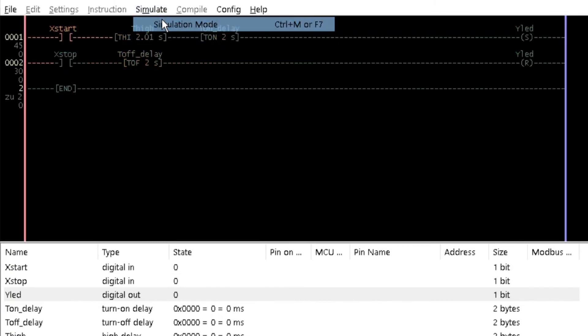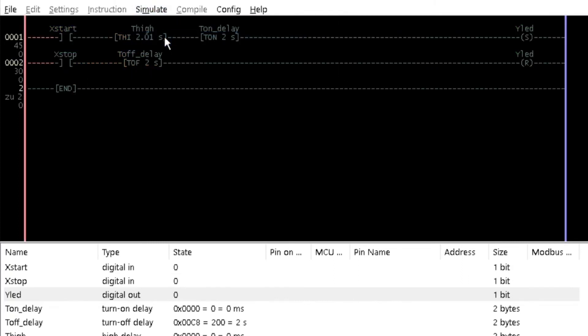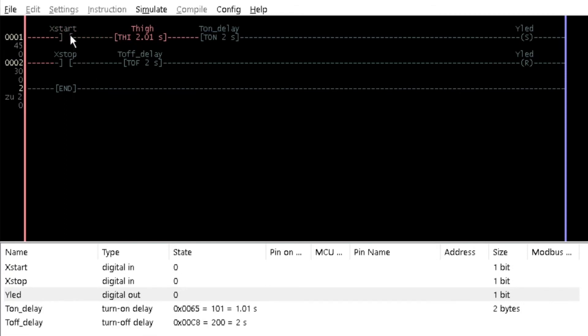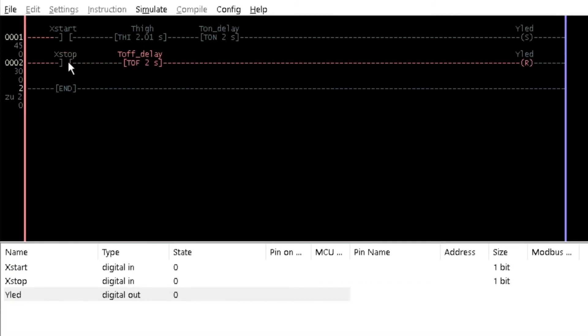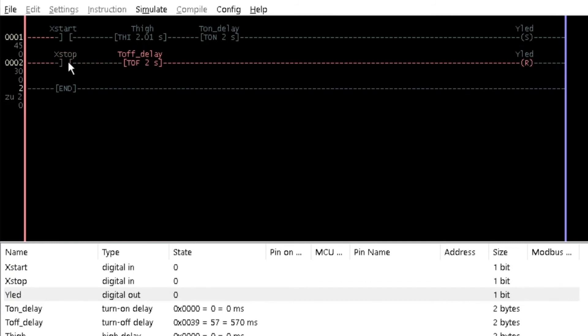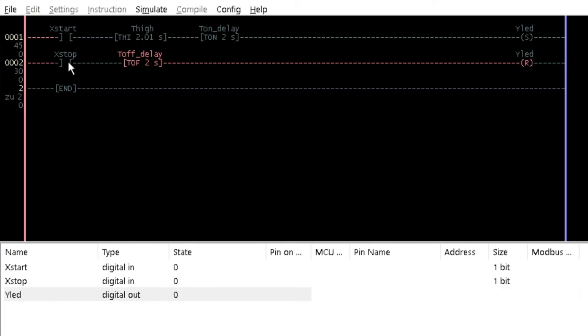Simulate the program and notice that Yled is delayed for 2 seconds when xStart is activated. The high duration extended by 10ms retains the xStart input signal to the timer to prevent a reset before the specified time interval elapses. When xStop is activated, a delay of 2 seconds is observed before Yled goes off.